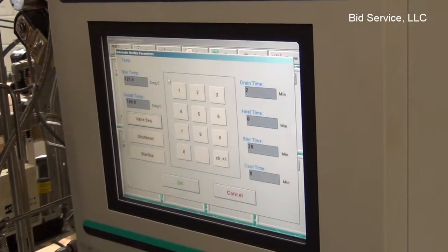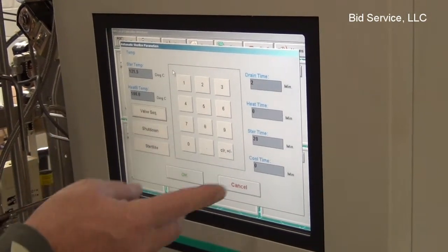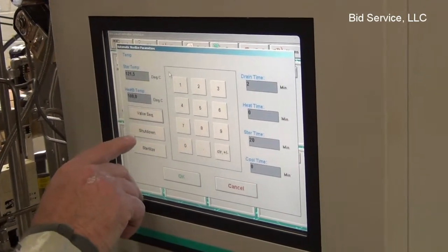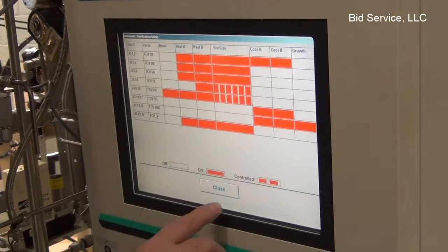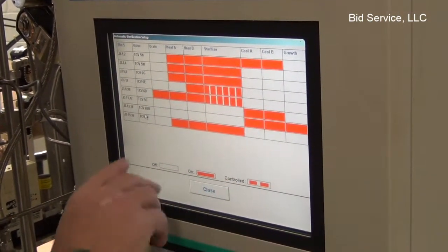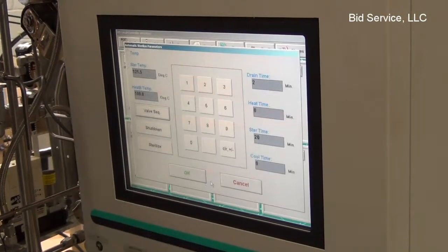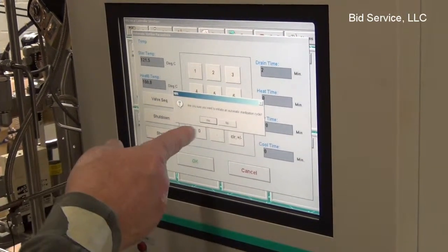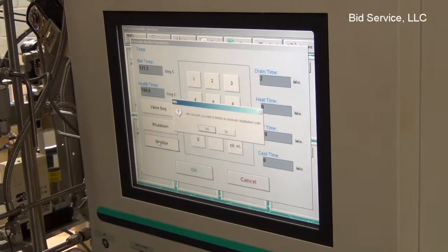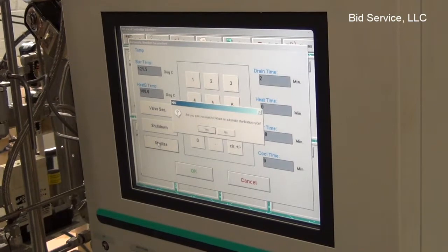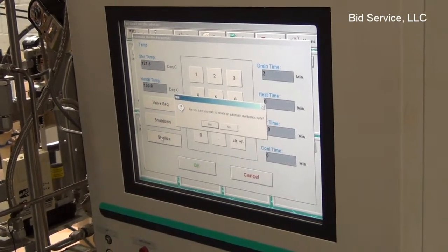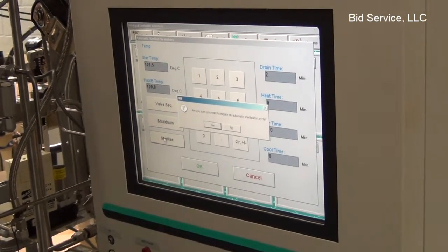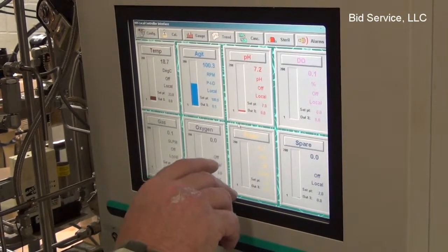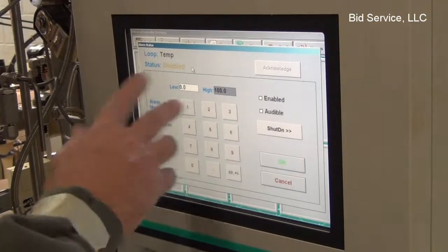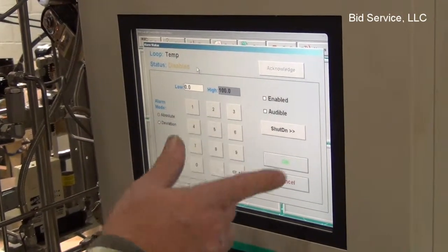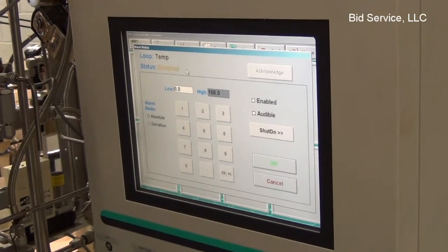Here's our sterilization program again. You can change your parameters in here to give you a sterilization process, and the valve sequencing appears here. Shows you that you have either an on, off, or controlled state, which is represented by the graphs in here. And then if you wanted to sterilize, you would just say you want to initiate an automatic sterilization cycle, and at which time you would need steam connected, and it would proceed to do that. You'd have to turn on your steam valves to make sure that those particular components that you wanted sterilized were contacted by the steam. We're not going to do that. Here's your alarms. Again, you could pick a loop, give it an alarm, enable it or disable it, make it audible, and if you wanted it to shut down that particular zone or the instrument.